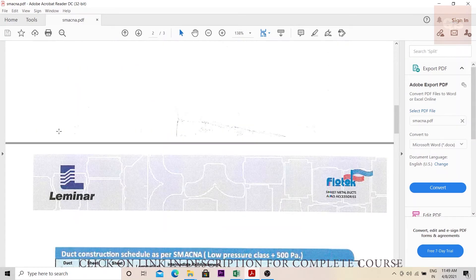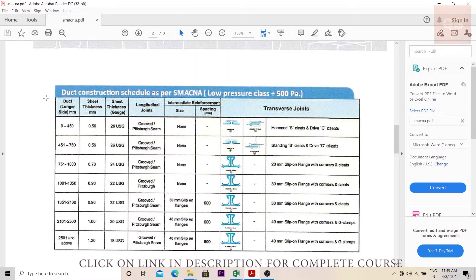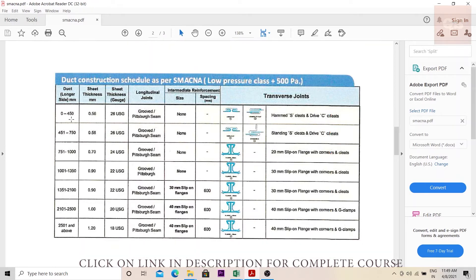Accordingly, you can determine which class the duct belongs to, and based on the standard used in the project, check that particular table. Here I am assuming the project follows SMACNA standards and is low pressure class. First, you need to find out the sizes of your duct — the width and height — which are given in your drawings.